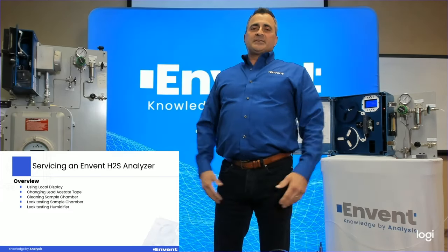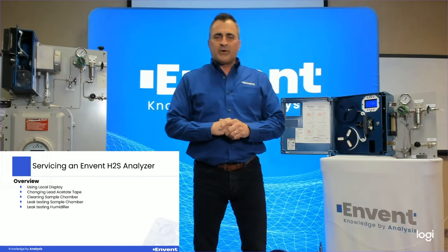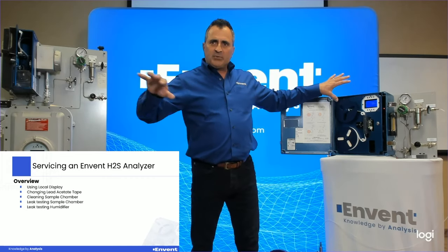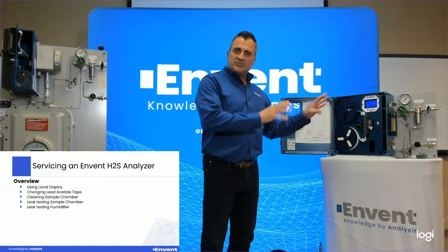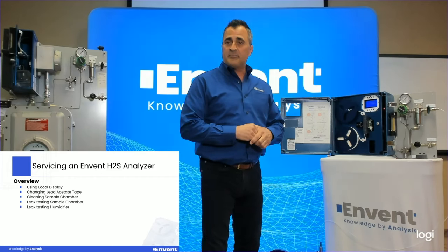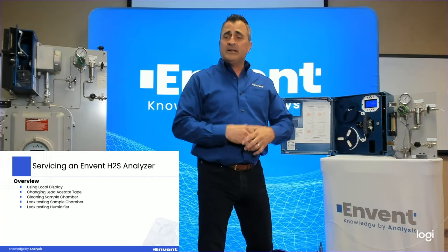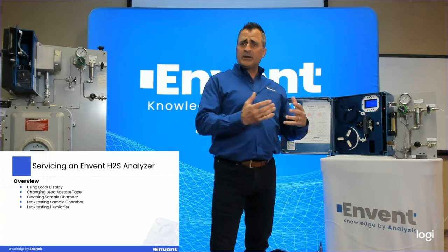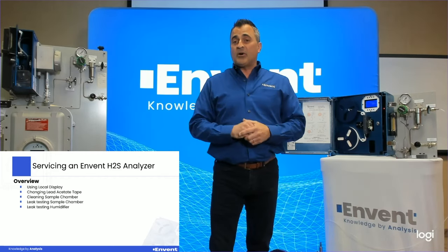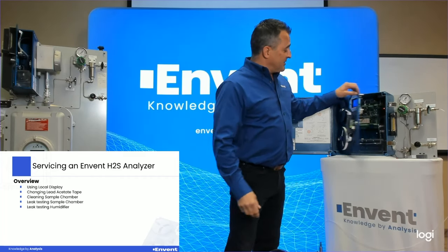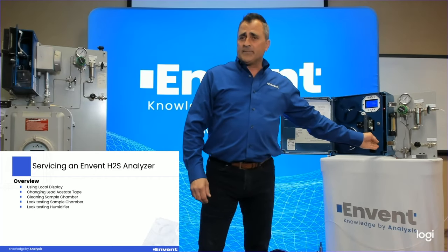This is where we get excited — we're going to service the Envent H2S Analyzer. Here's a quick overview: we're going to briefly use the local display, change the lead acetate tape with a cool trick I've learned over the years, clean the sample chamber — pull it out, pull the sensor off, and show you how simple it really is — then do a leak test on the sample chamber, and finally leak test the humidifier.